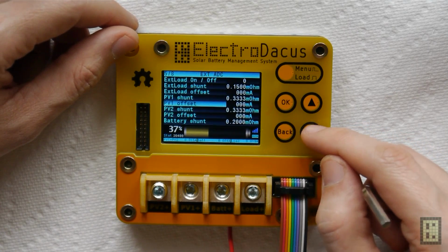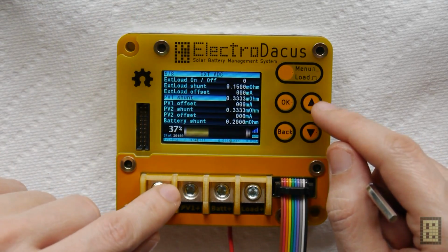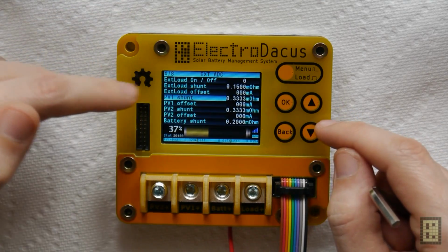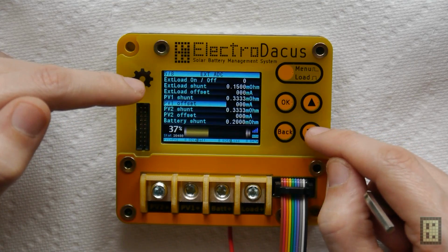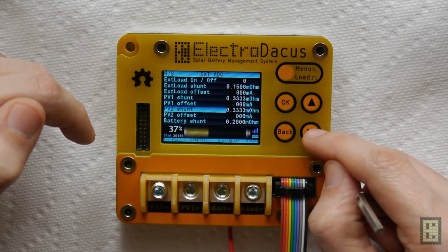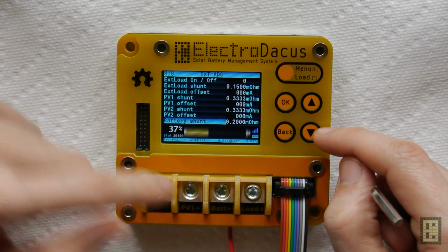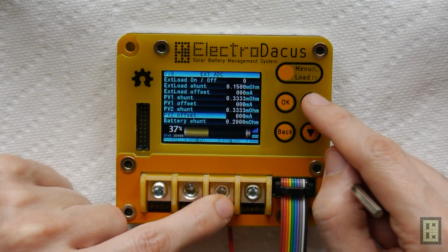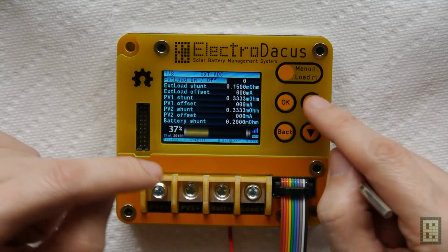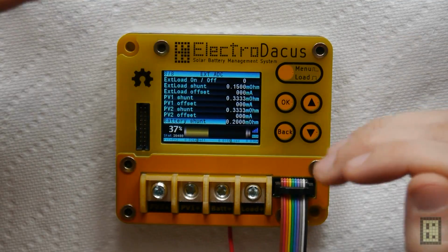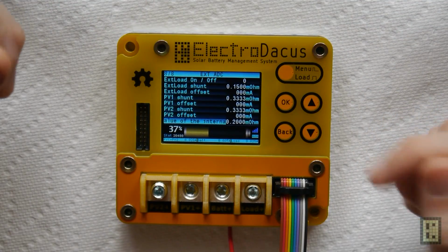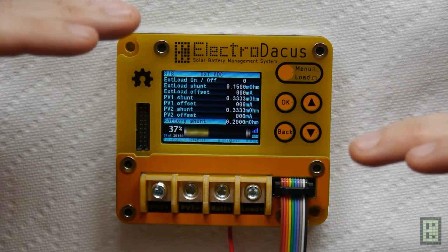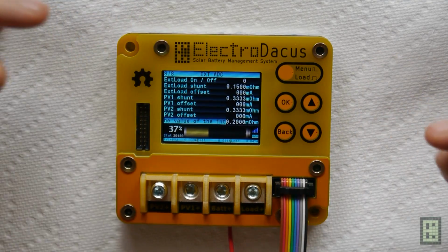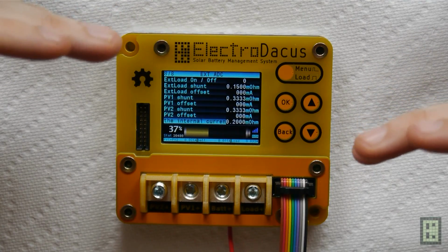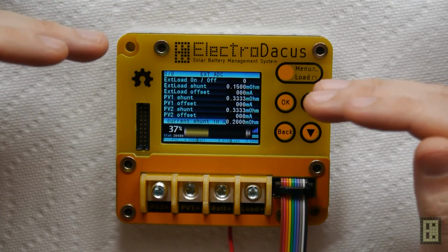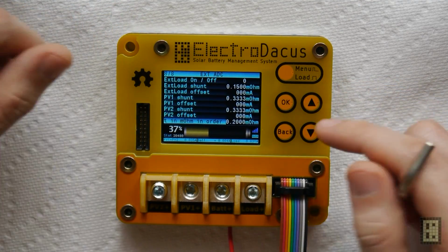I did the same for the internal current shunts. The internal current shunt is 0.33 milliohm for both PV inputs and 0.2 milliohm for the battery current shunt. Since the battery current shunt is bidirectional, measuring both negative and positive currents, it will calibrate the offset automatically no matter what type of offset the current sense amplifier has, so there's no problem there.